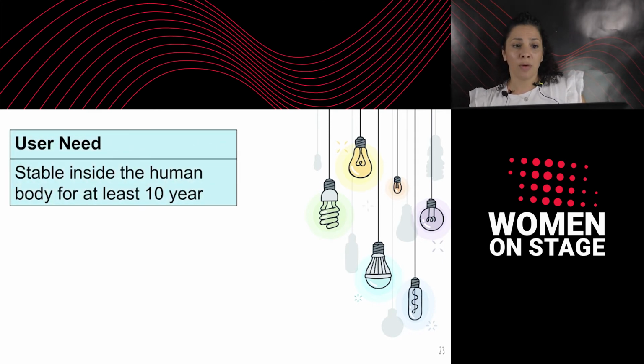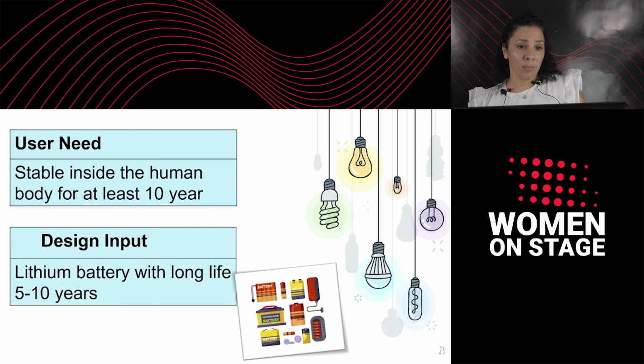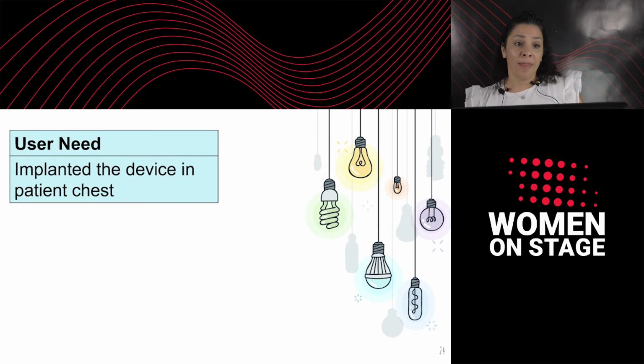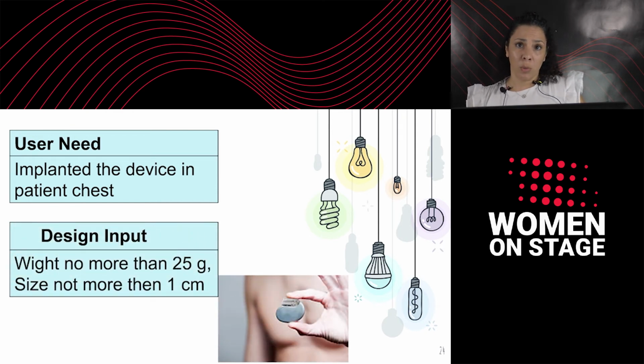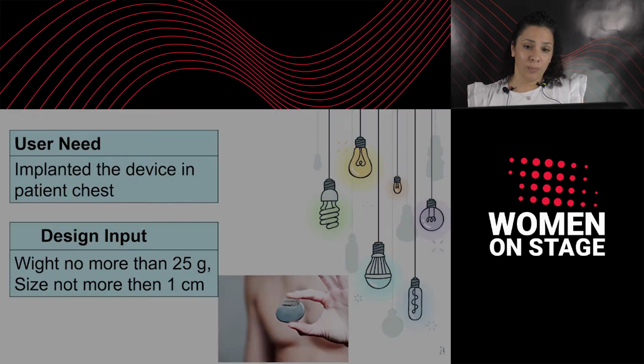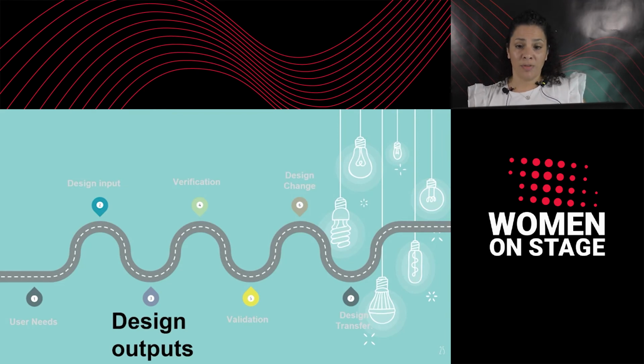Pacemaker example: an input can be, since the pacemaker should be stable in the human body for at least 10 years, we need a suitable material to support it. Therefore, one related input may be that the battery will be lithium with long life, 5 to 10 years. Or another example is that the device should be implanted in the patient's chest. Therefore, it should be small and light. So the input may be that the weight will be no more than 25 grams and the size not more than 1 centimeter. Remember that you should consider design verification when establishing the inputs. But before jumping to the verification, we'll have a short stop in the design output station.